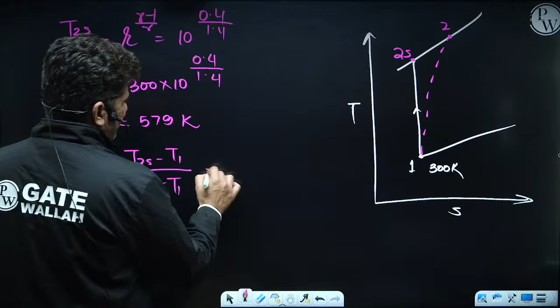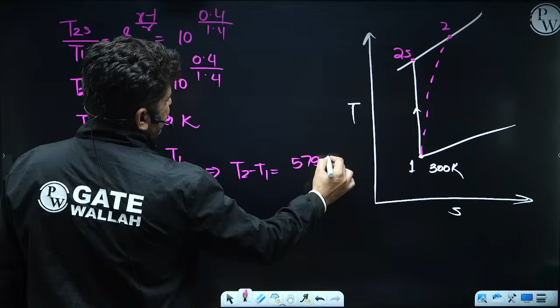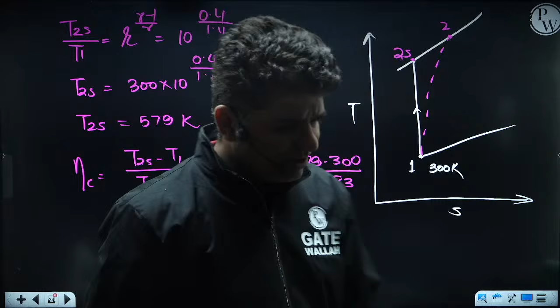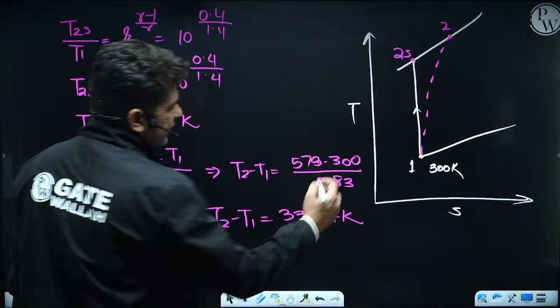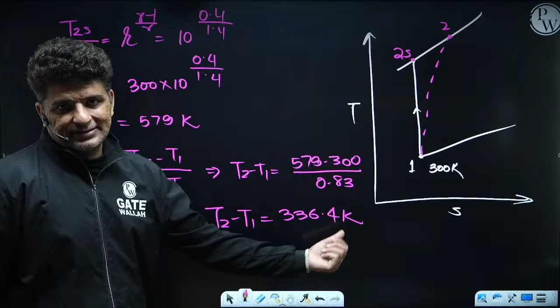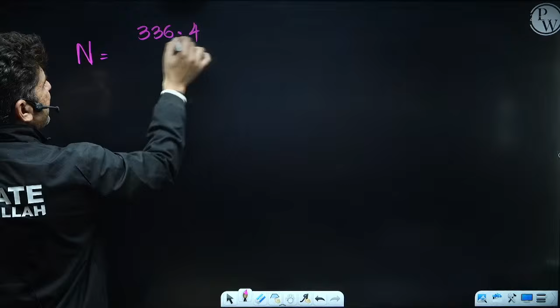So from here you can calculate T2 minus T1, which will be equal to (579 minus 300) divided by 0.83. How much is coming? It will come out to 336.4 Kelvin. So the temperature rise across all the stages is 336.4. The number of stages will be equal to the total temperature rise, 336.4, divided by the temperature rise across each stage, 20 Kelvin. So N would come out to be about 16.8.